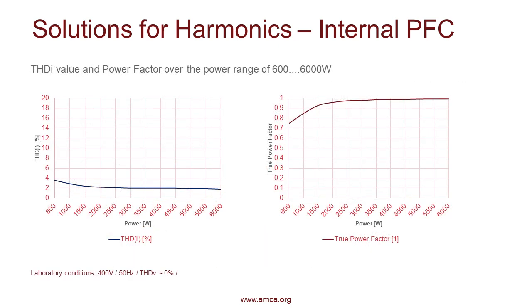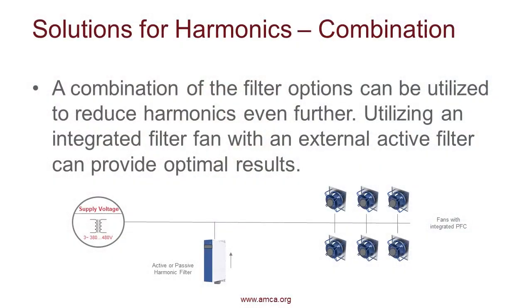And we can look at an example under laboratory conditions, 600 to 6,000 watts. We can see that the total harmonic distortion current is now less than 4% for the entire 600 to 6,000 watt power range. And we can see that the power factor is fairly close to that 1 for a majority of that range. And now we can see, okay, maybe we need to have a combination of these. So an active or passive harmonic filter utilized with fans that have the integrated PFC.